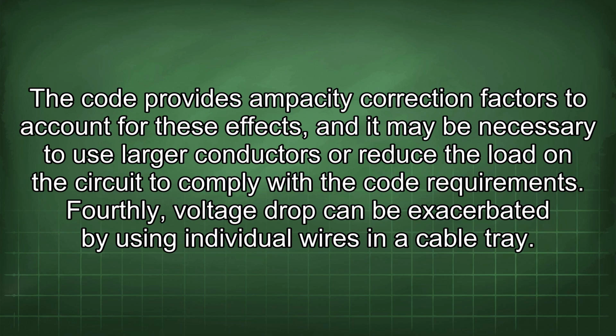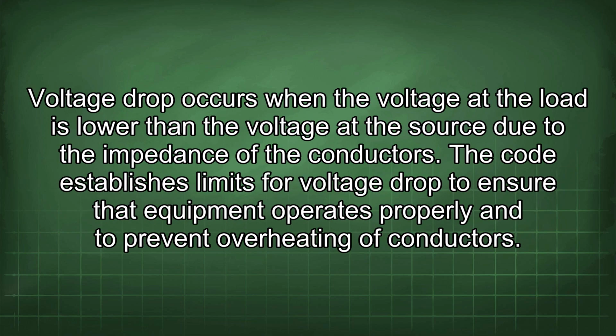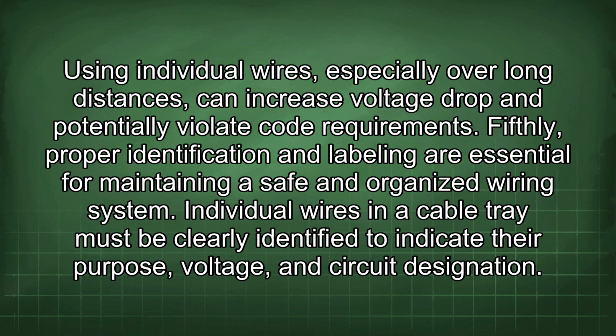Fourthly, voltage drop can be exacerbated by using individual wires in a cable tray. Voltage drop occurs when the voltage at the load is lower than the voltage at the source due to the impedance of the conductors. The code establishes limits for voltage drop to ensure that equipment operates properly and to prevent overheating of conductors. Using individual wires, especially over long distances, can increase voltage drop and potentially violate code requirements.